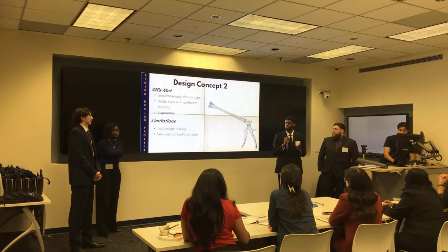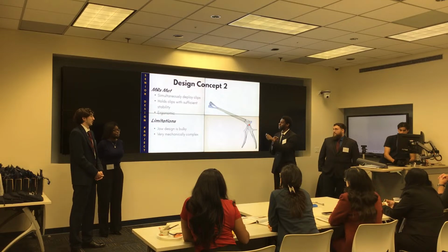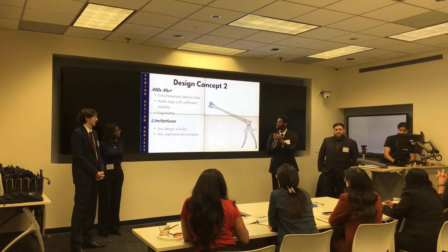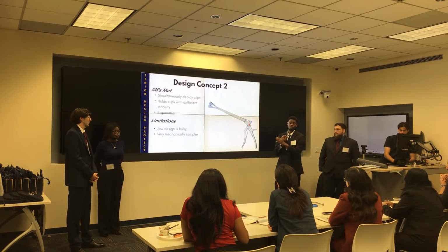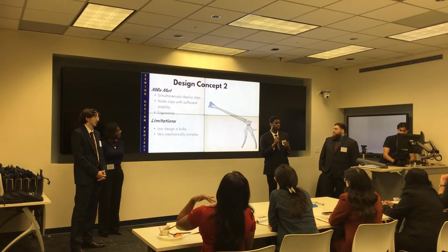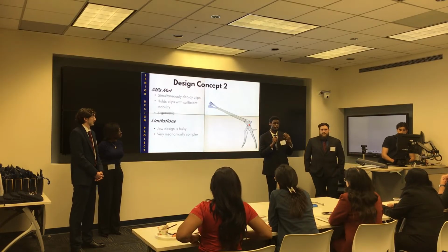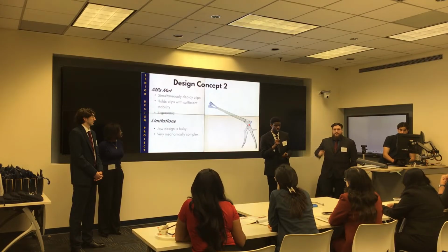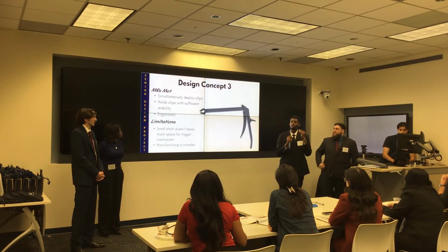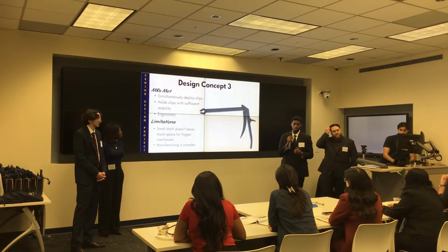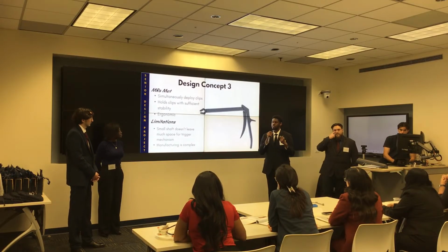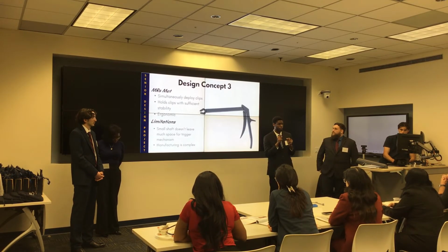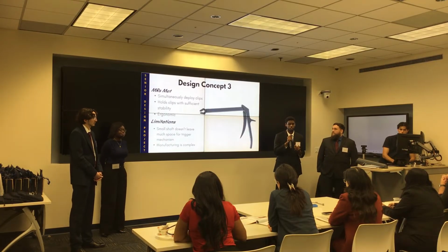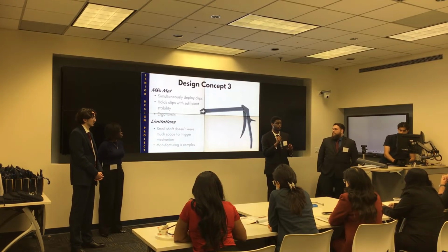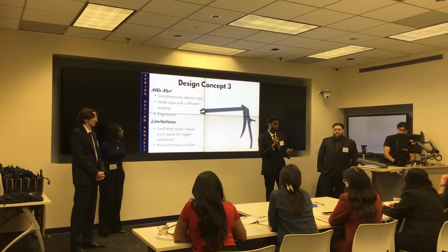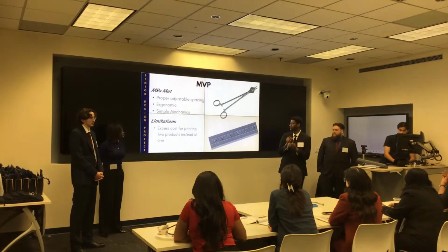To combat these issues with the first design concept, we decided to slim down the body of our device and increase the size of the jaw in order to prevent fluid ingress into the device. However, this increased jaw size did cause impairment in the field of view of the surgeon. To combat this, we completely shrunk down the size of our device. However, this caused the internal mechanical components in our device to be so small and precise that it increased the manufacturing cost, which was something that we were very cautious of during our design process. This led us to our MVP design.